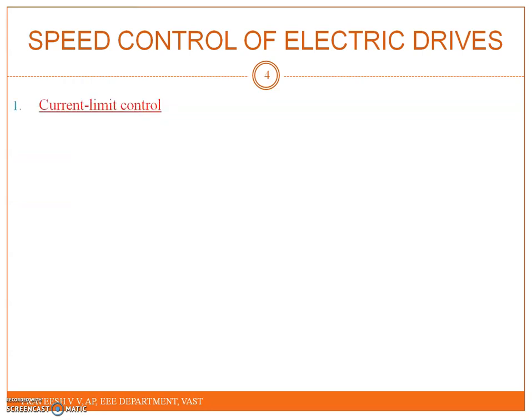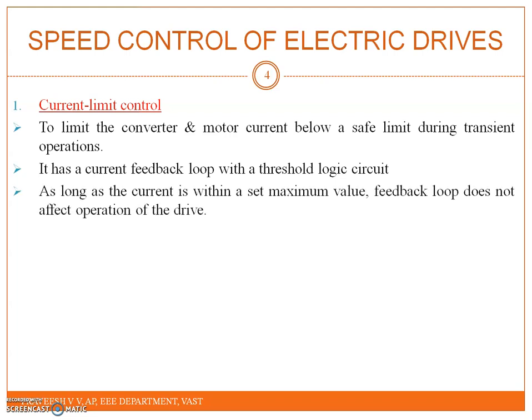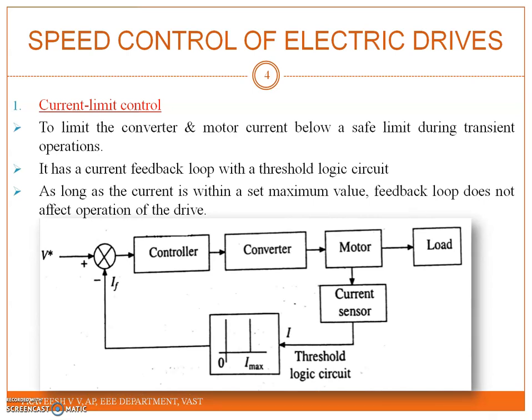The first case is current limit control, which limits the converter and motor current below the safe limit during transient operations. This uses a current feedback loop with a threshold logic circuit. As long as the current is within the set maximum value, the feedback loop does not affect the normal operation of the converter.